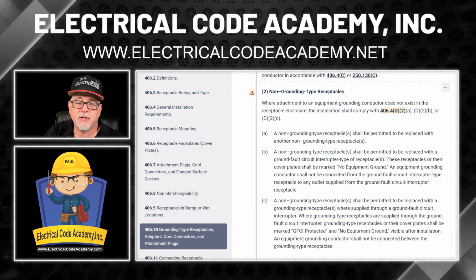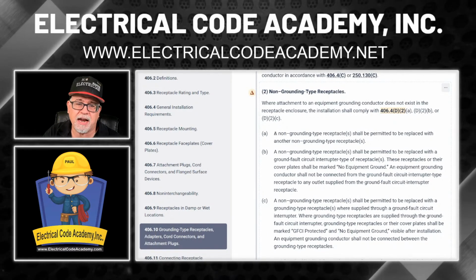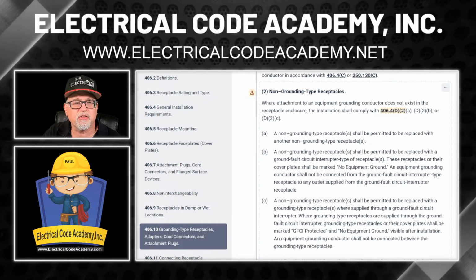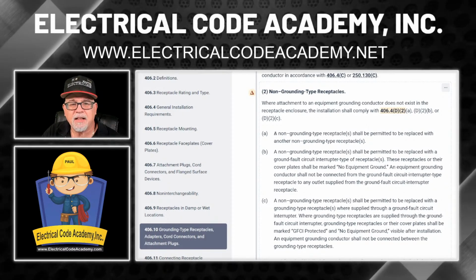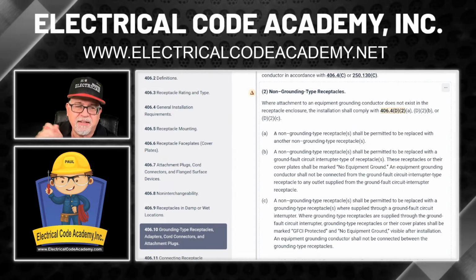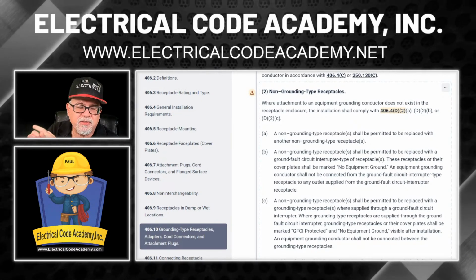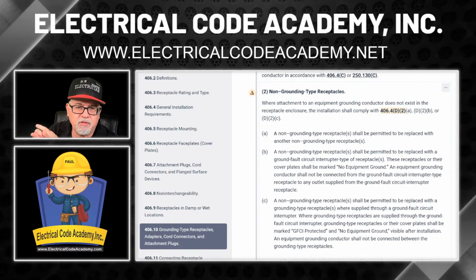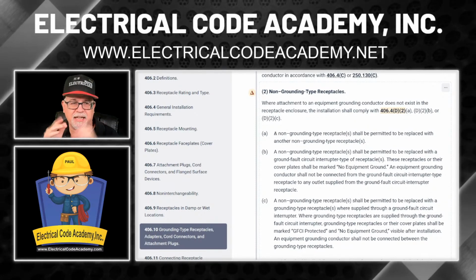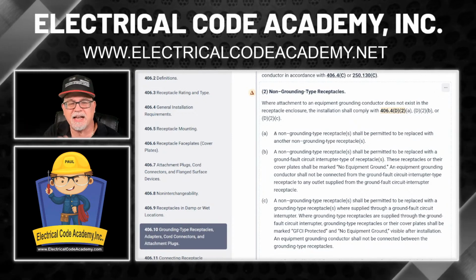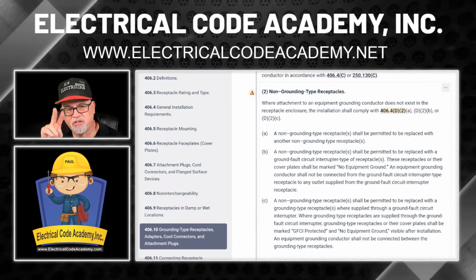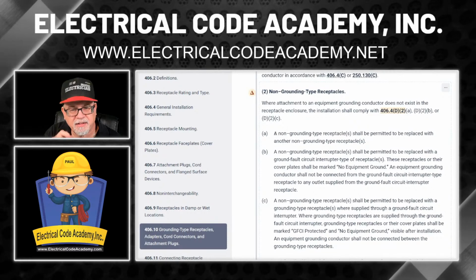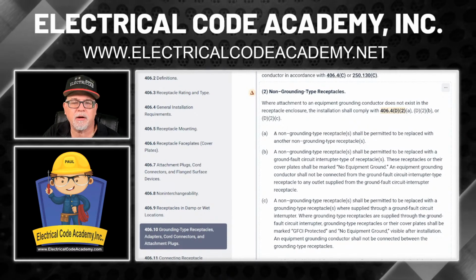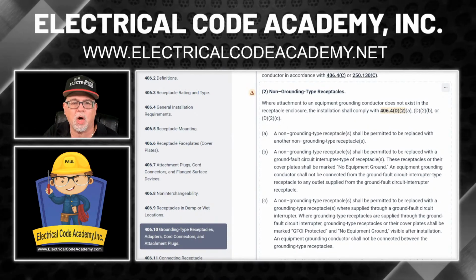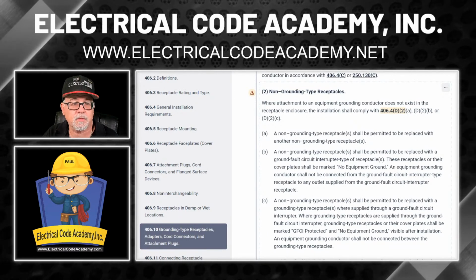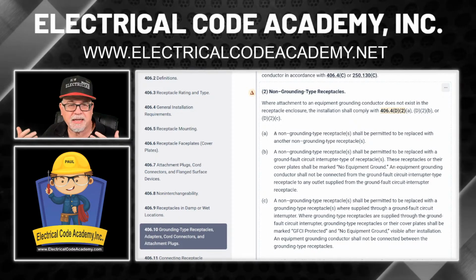But instead of just putting a label on there that says no equipment ground, on all those receptacles that are supplied from the GFCI device, they have to have GFCI protected put on them, and they also have a label that says no equipment ground, just like the one if you just put a single receptacle in like he did. So if you're going to be protecting any downstream from that device, then it's going to need 2 labels on it. One that says GFCI protected, and one that says no equipment ground. Okay, and they have to be visible on the actual cover plate or the device. Okay, so typically, that's what you'll see.